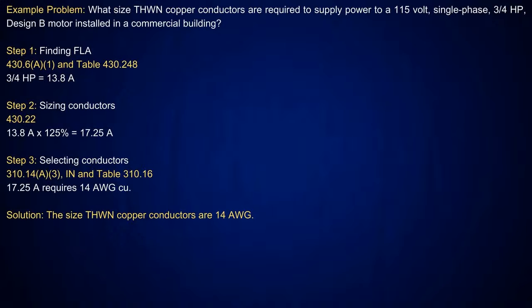Now that got us through that. Now, what we're going to get into is looking at motors. Now, we're going to start this off a little bit different. Everything I've done up to this point, I've based off of looking at 240.4(B) for overcurrent devices 800 amps or less and 240.4(C). That was just how we went about the overcurrent protection devices, because sometimes we need to do that to make sure we're matching up with the size for calculating my conductor ampacities. This one here is going to be a little bit different, and this is going to be a prelude to what we're going to do in the next part, where we get into sizing overcurrent protection devices.